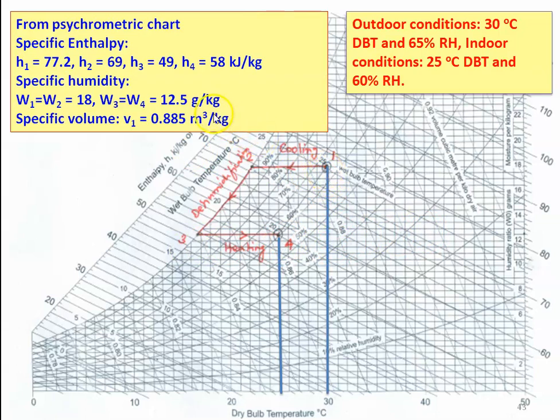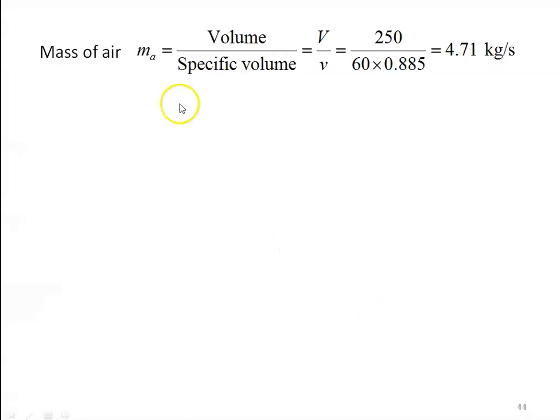The properties collected from the psychrometric chart are: H1 = 77.2 kJ/kg, H2 = 69 kJ/kg, H3 = 49 kJ/kg, H4 = 58 kJ/kg. The specific volume of air at the inlet condition (point 1) is 0.885 m³/kg. The mass of air equals volume divided by specific volume: 250 m³/min divided by 60 (to convert to per second), divided by 0.885, giving a mass flow of 4.71 kg/s.